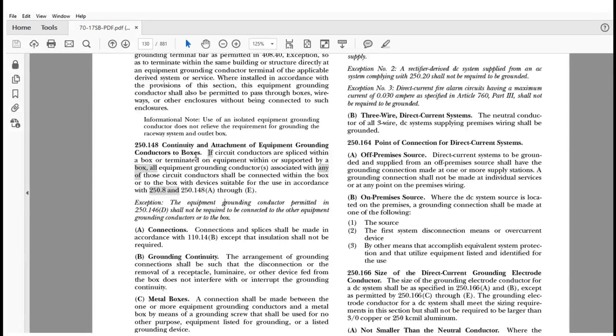All right, let's get to the core of this. This revision clarifies that all equipment grounding conductors that are associated with any of the circuits that come to that box must be connected together. There were many times where we saw people send me emails or questions. I had inspectors call me and say, wait a minute, I'm in a kitchen and they've got a 14 gauge coming in for the lighting and they got a 12 gauge for the kitchen circuits, and they isolated them away.